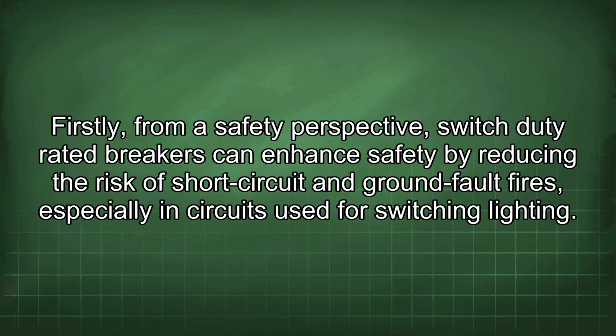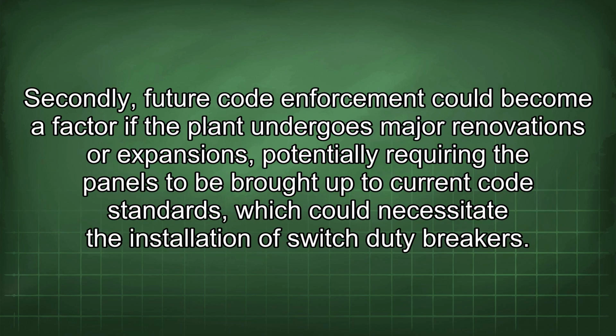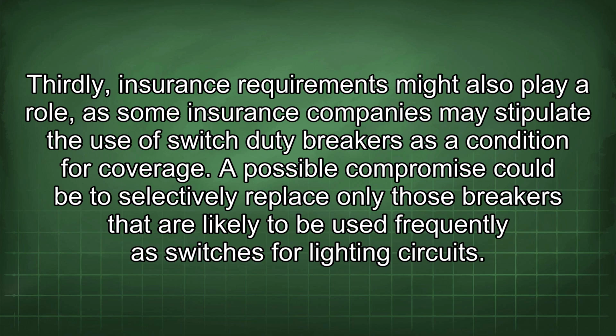However, there are also considerations that argue for the replacement of breakers with switch duty ratings. Firstly, from a safety perspective, switch duty rated breakers can enhance safety by reducing the risk of short circuit and ground fault fires, especially in circuits used for switching lighting. Secondly, future code enforcement could become a factor if the plant undergoes major renovations or expansions, potentially requiring the panels to be brought up to current code standards, which could necessitate the installation of switch duty breakers. Thirdly, insurance requirements might also play a role, as some insurance companies may stipulate the use of switch duty breakers as a condition for coverage.